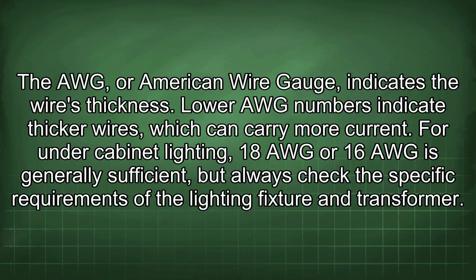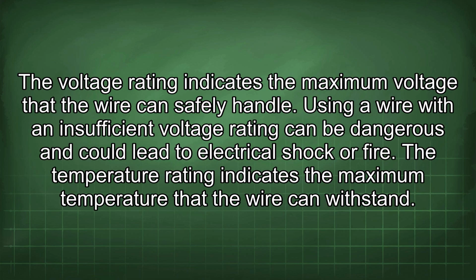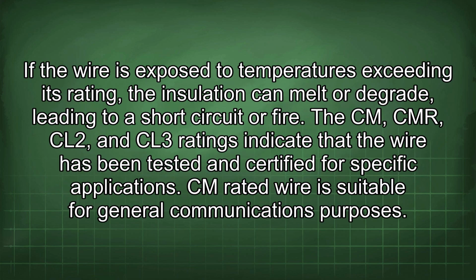For under-cabinet lighting, 18 AWG or 16 AWG is generally sufficient, but always check the specific requirements of the lighting fixture and transformer. The voltage rating indicates the maximum voltage that the wire can safely handle. Using a wire with an insufficient voltage rating can be dangerous and could lead to electrical shock or fire. The temperature rating indicates the maximum temperature that the wire can withstand. If the wire is exposed to temperatures exceeding its rating, the insulation can melt or degrade, leading to a short circuit or fire.